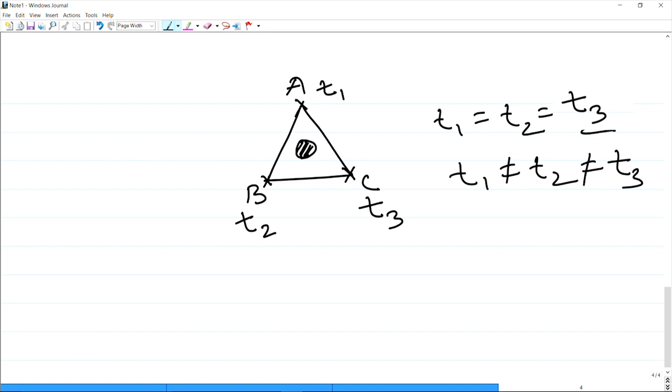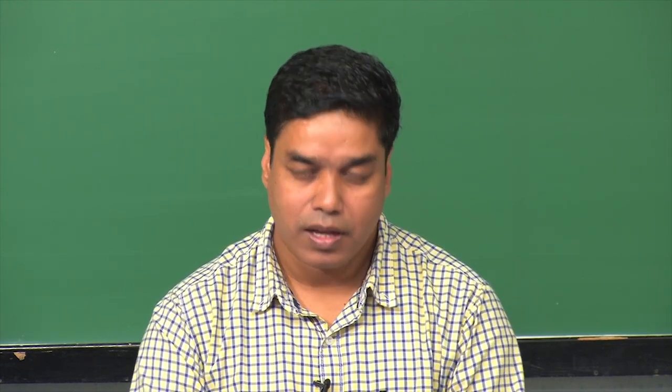When you place a number of sensors around particular locations, the different arrival times at each sensor give you an idea of the zone or location from where the acoustic emission signals are coming out. This is how the zonal location technique indicates the zone of emission. Accordingly, you should target those areas while inspecting and taking corrective measures.